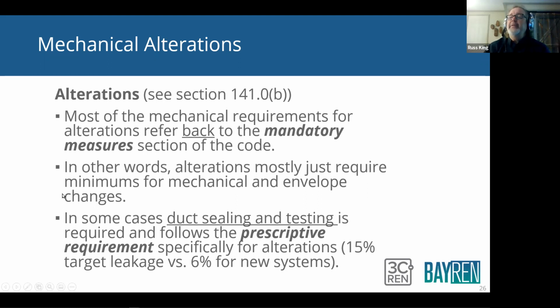In some cases, duct sealing and testing is required and follows a prescriptive requirement. So there are some additional prescriptive requirements. For alterations, you have to seal the ducts to 15%, and for new construction, you have to seal the ducts to 6% of airflow, okay?